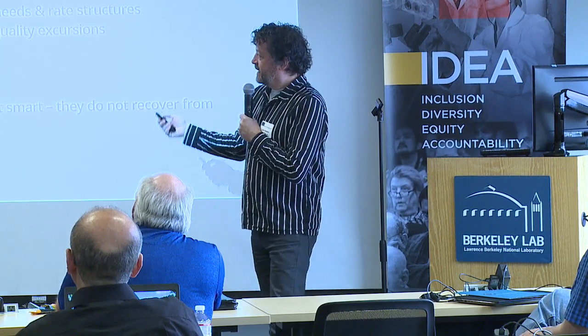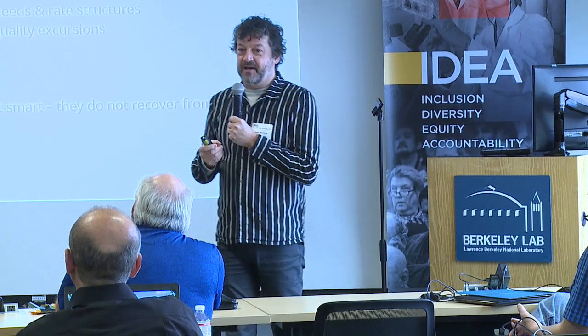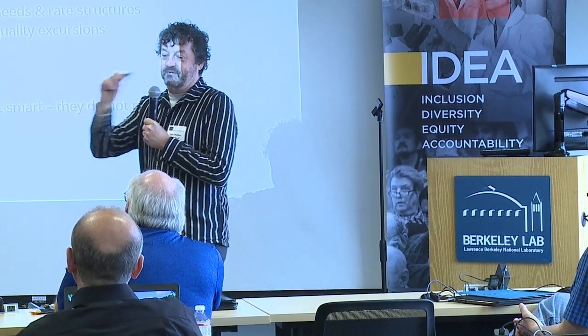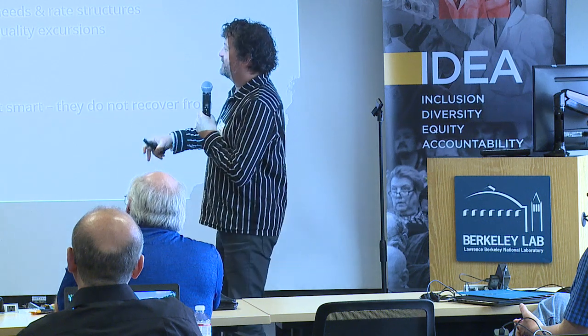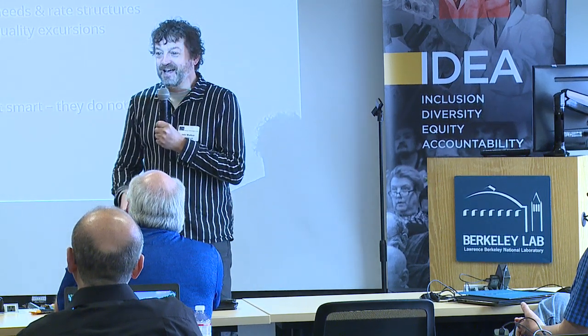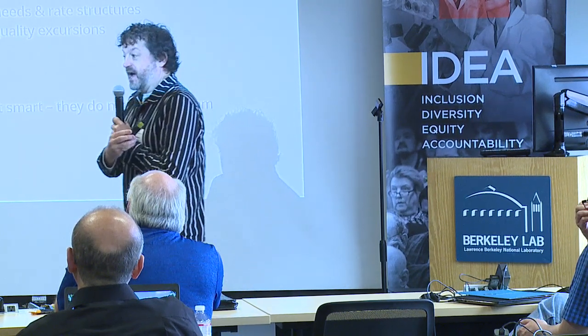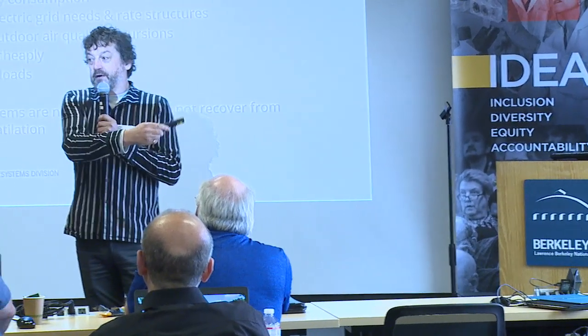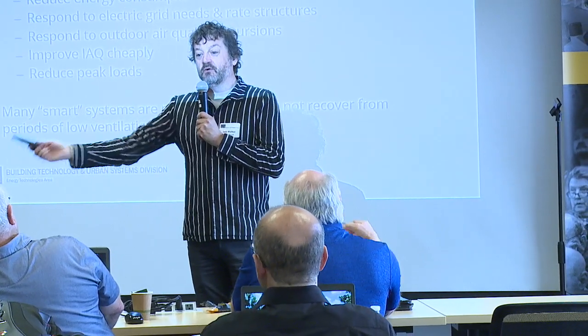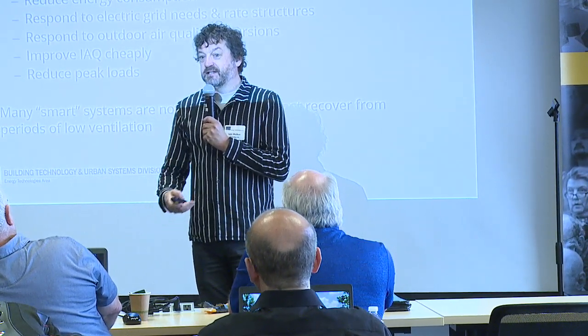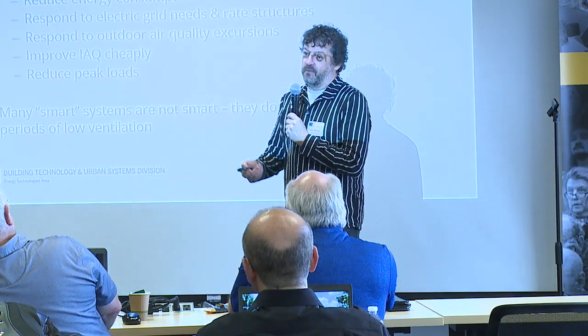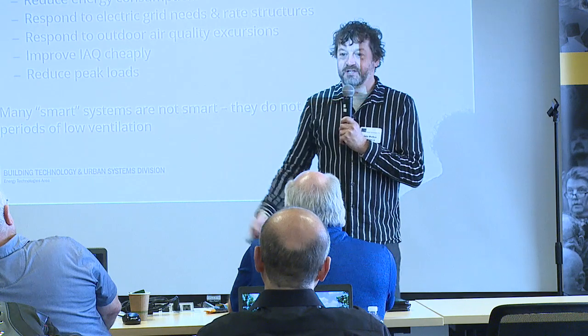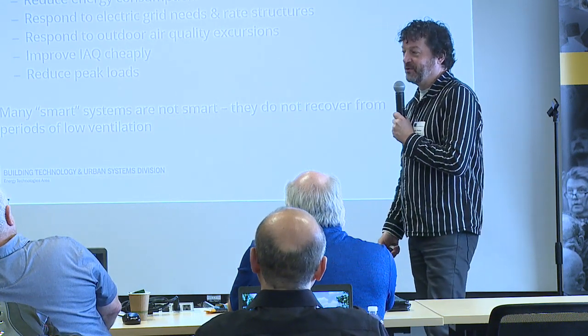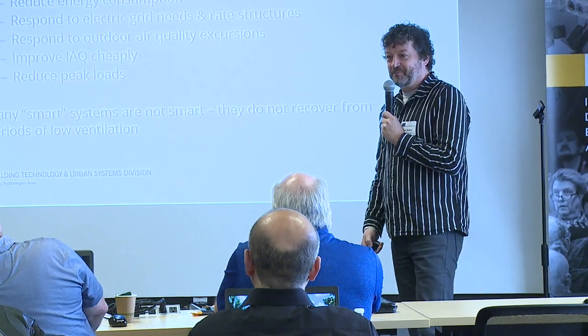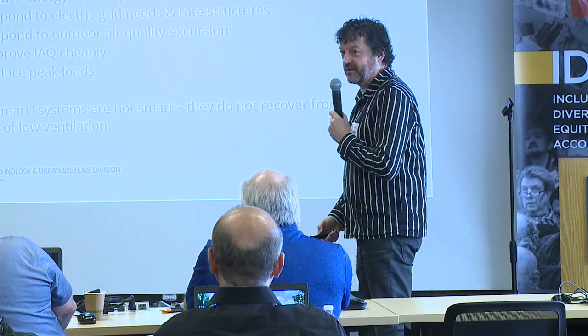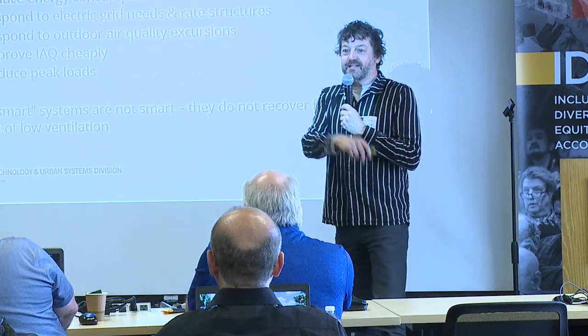The caution is, a lot of manufacturers decided smart ventilation sounds great, so they put that label on everything. Many labels you see for smart ventilation don't do any of the good things I just described. The key thing they actually do is respond to outdoor conditions - like turning off ventilation if it's very cold outside. What they don't do is make up for that later. So that's a trade-off: you save energy, but the air quality is worse. You can always turn stuff off to save energy, right? It doesn't get you anywhere. You can always not heat a building - it won't be comfortable, but you'll save energy. You could turn all the lights off, but it'll be dark at night. That's no way to go.